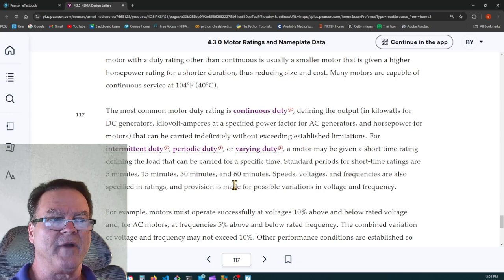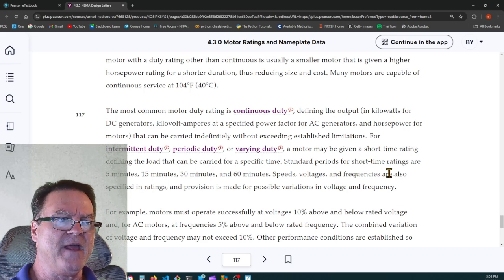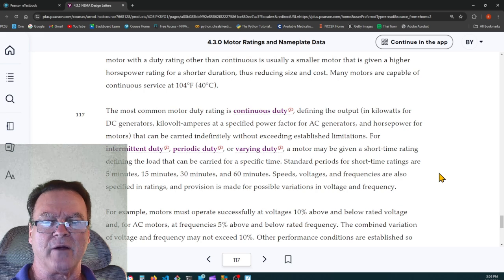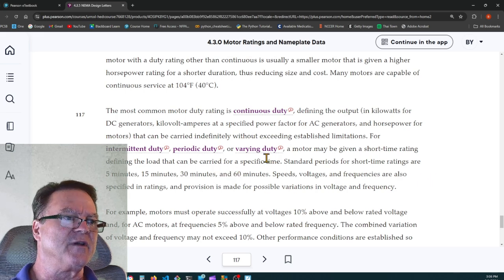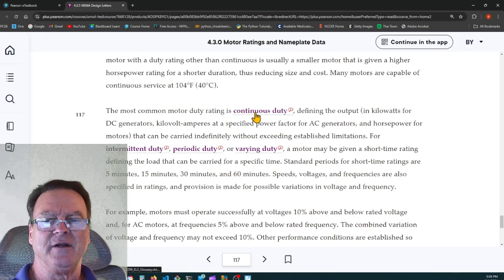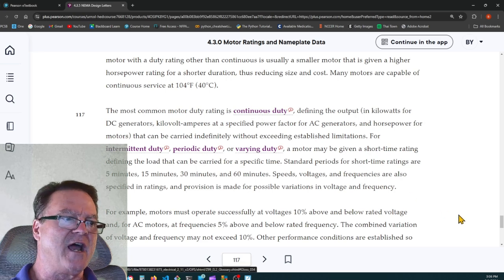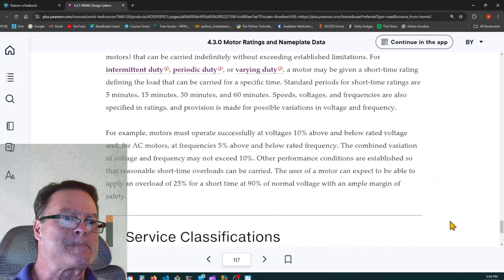If you have a pool pump, that's going to be continuous duty because they understand that sometimes people will turn on their pool and want it to run for 3 or 4 hours. They will rate that at continuous. They're not going to give you a 60-minute time limit on your pool pump.